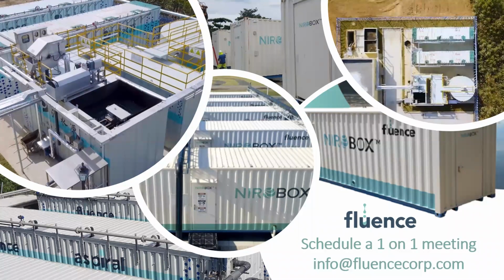A building block, like I said, has quite a few different models for the Aspiral MABR biological wastewater treatment plant. It could be designed with a higher load or lower load, and a couple of other parameters to produce higher or lower quality effluent, and that also influences, together with temperature and other parameters, the HRT or the size to meet a certain specification. I hope this answered in part, but in any case, of course, we can handle any specific request.